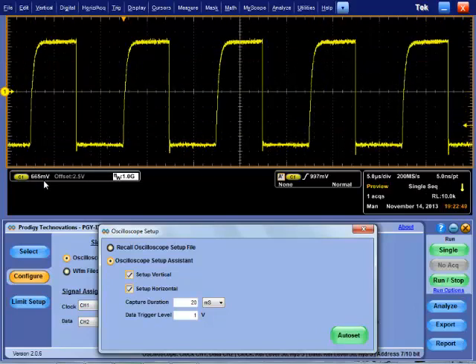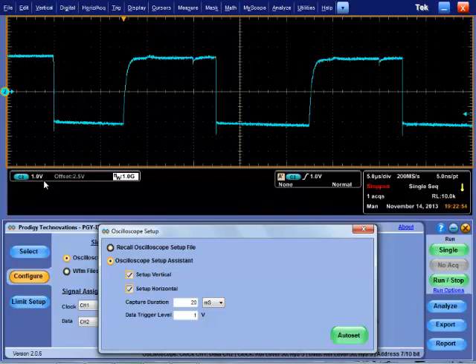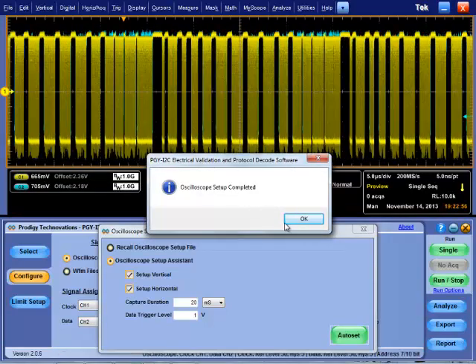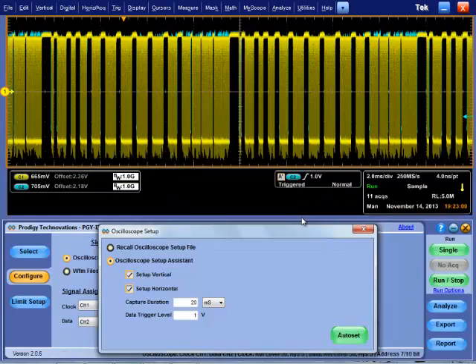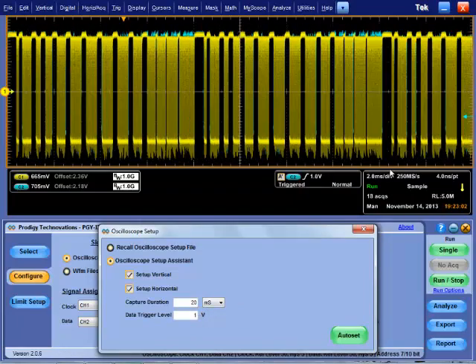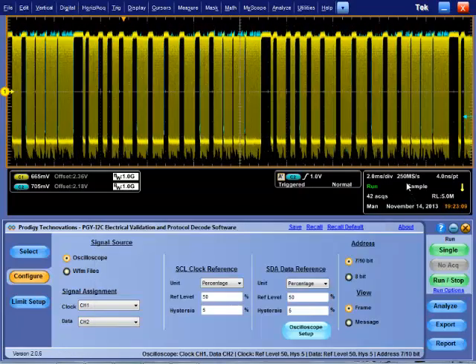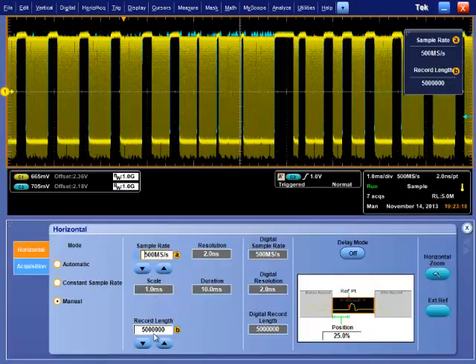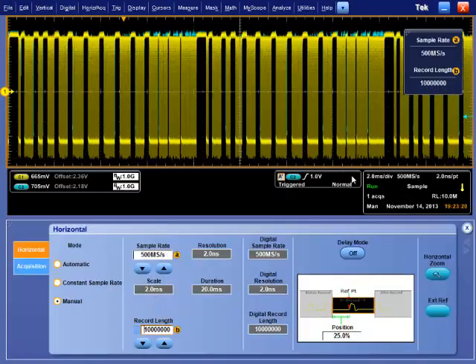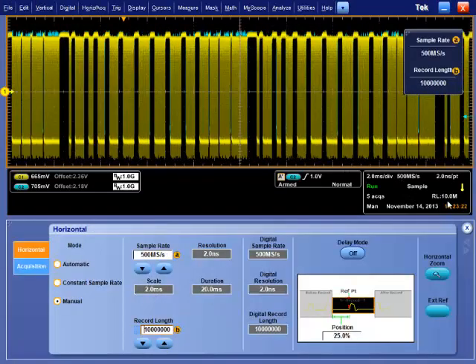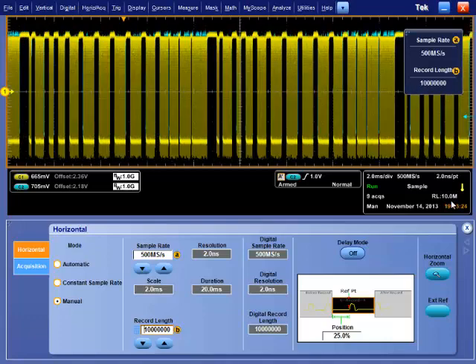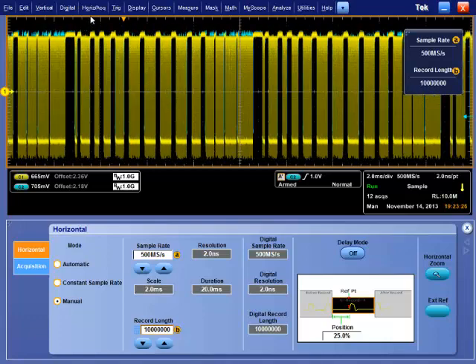Capture duration helps in setting record length. To further increase the sample rate, go to the horizontal menu of oscilloscope and increase the sample rate. To increase capture duration, increase the record length. Now, your vertical and horizontal setup is complete.